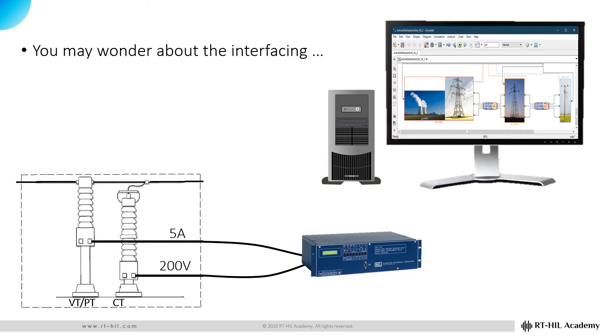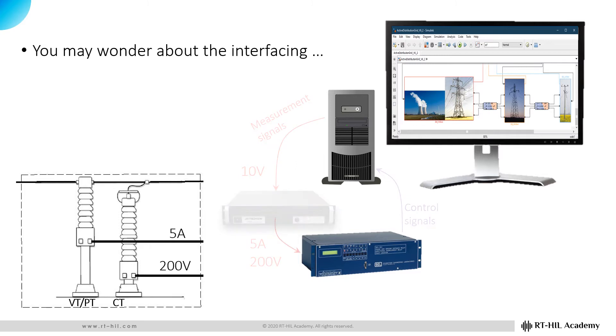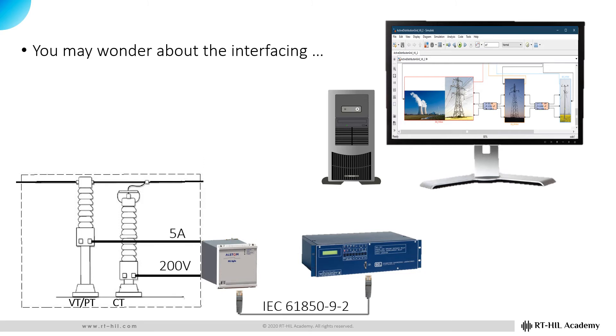The problem is that the analog signals provided by the real-time simulator are limited within a few volts, so a current or a voltage amplifier is needed to scale them up to the level that becomes meaningful to the actual device. The control signals sent back to the simulator may or may not need an interface, depending on their magnitude. With the advent of communication-based architectures for industrial plants, the devices in actual plants are nowadays interfaced through communication networks, rather than analog or digital signals.